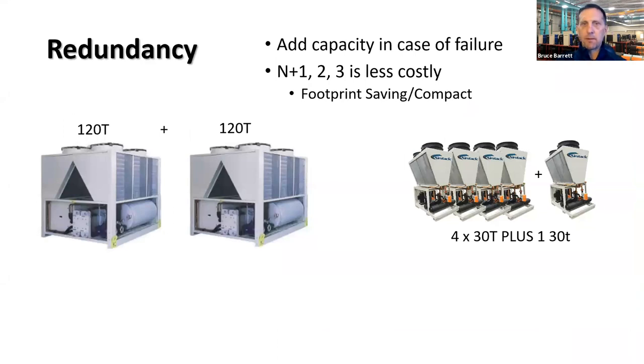So redundancy, let's spend a few minutes talking about that. A typical redundant air-cooled system may require, in this case, 120 tons as your load. You need a full chiller of 120 tons as backup. If one of the other chillers fails, you're back down to 120 tons. The modular concept is a lot easier. It saves a lot of footprint. Footprint can mean installed cost.